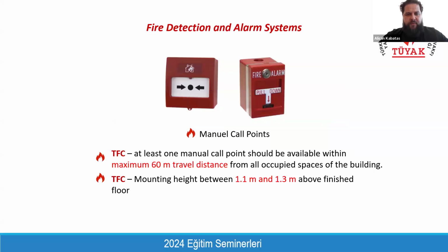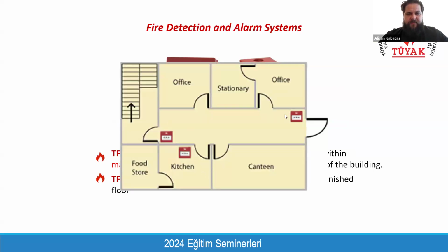And we will have manual call points, which is not architecturally good-looking equipment, but it's mandatory. It should be mounted between 1.1 and 1.3 meters so that everyone can use it. And you will see it on your main corridors. There is no other alternative to these manual call points. And as you can see, at the entrance to the exit access routes, just next to the exit access doors, we will have some manual fire call points.